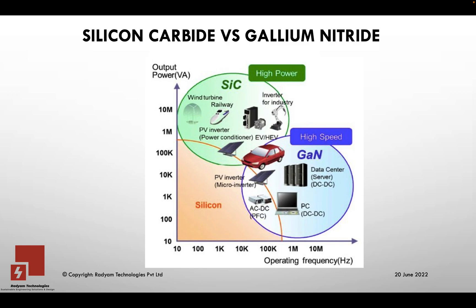We'll take a look at some limitations on silicon devices that we currently use — either IGBTs or MOSFETs — which are mainly focused towards lower operating frequencies, with IGBTs operating optimally around 20 kilohertz. You can extend the range up to probably 100 kHz with a good MOSFET, but if you want to go higher in voltage or frequency, then Silicon Carbide and Gallium Nitride are two viable devices that have come into play with good cost.